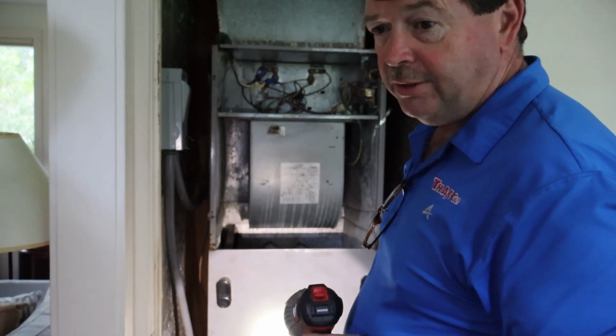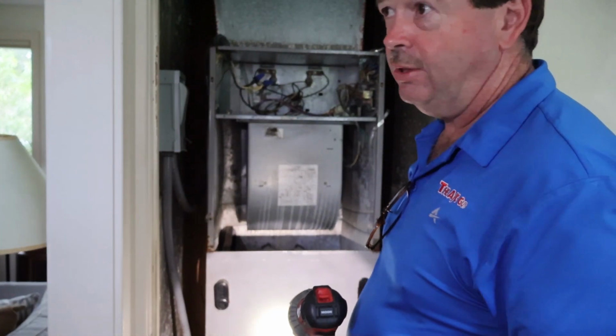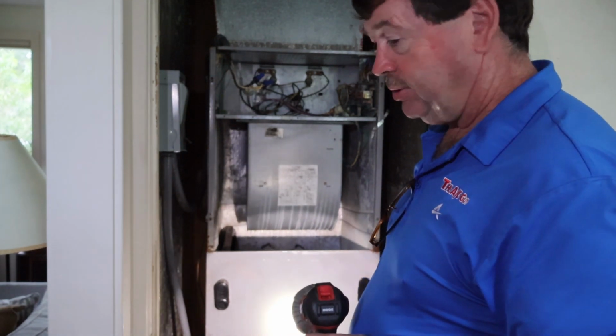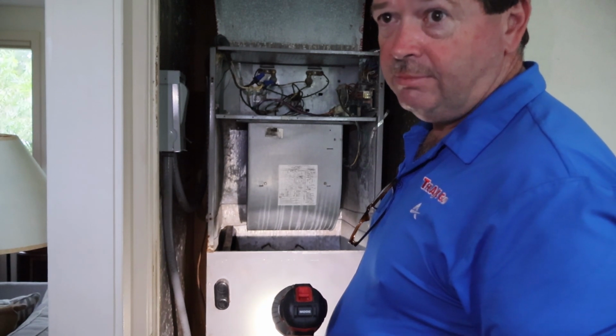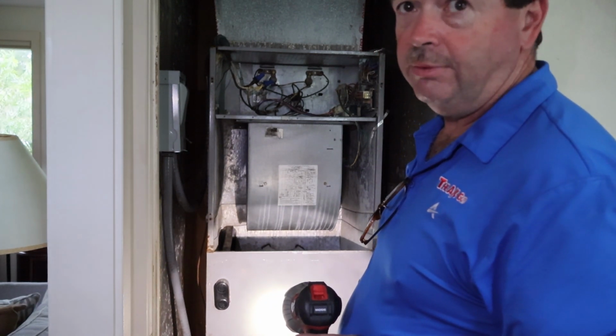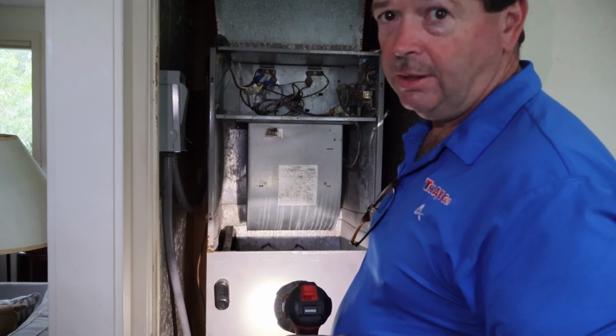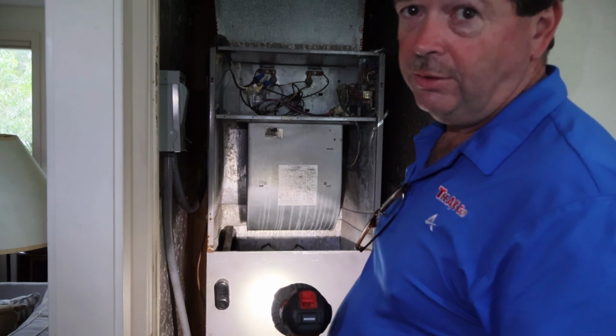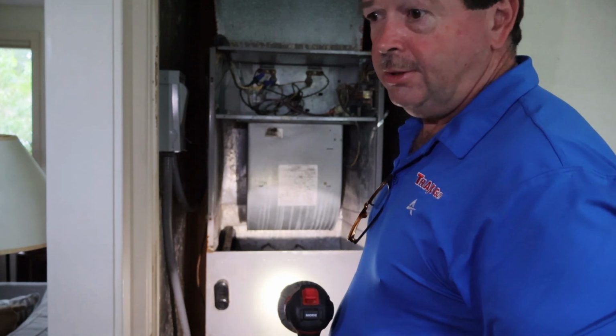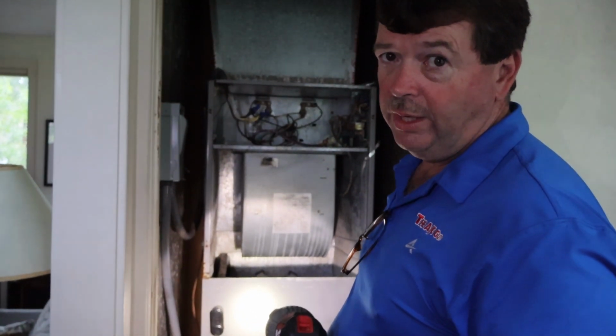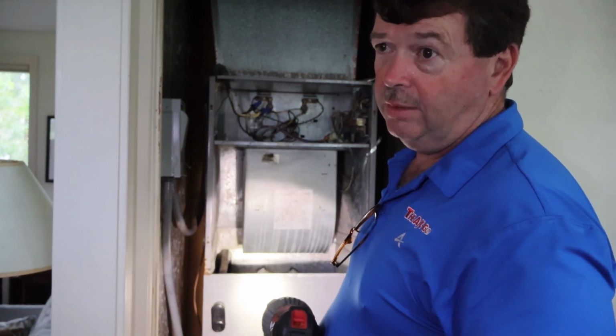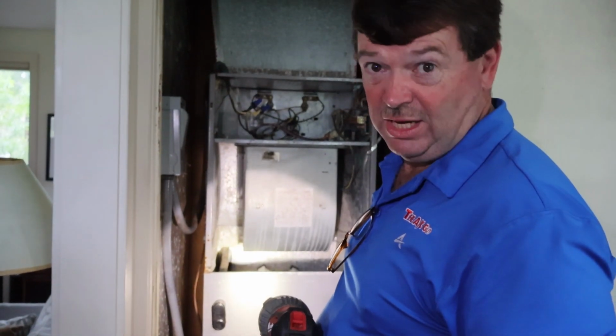It's good to have the primary drain insulated, keeps it from sweating on the ceiling, so you can make that recommendation to the customer. Make sure there are no bellies, no traps in the drain that you can see from the attic. Very important, to prevent the drain backing up and causing problems, especially when we've just recently done a maintenance. It's hard to explain whenever we just flushed the line, but let the customer know they could potentially have a problematic drain because it's real long or it's got a lot of bellies in it, and so on and so forth. Just good advice, but keep the customer aware of these problems or potential problems. Write it down, type it into your work order, whatever you've got to do, so they can see it in the building. All right, and collect, and we'll do that next video.